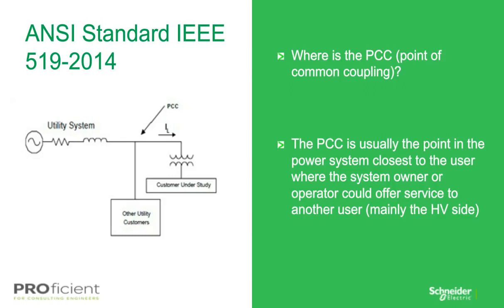So for the 2014 standard, IEEE defines it as follows: the limits in this recommended practice are intended for applications at the point of common coupling between the system owner or operator and a user. The PCC is usually taken at the point in the power system closest to the user where the system owner or operator could offer service to another user. Frequently, service to industrial users, i.e. manufacturing plants, is through a dedicated service transformer. The PCC is at the high voltage side of the transformer. For commercial users, office parks, shopping malls, etc., supplied through a common service transformer, the PCC is commonly at the low voltage side of the service transformer.